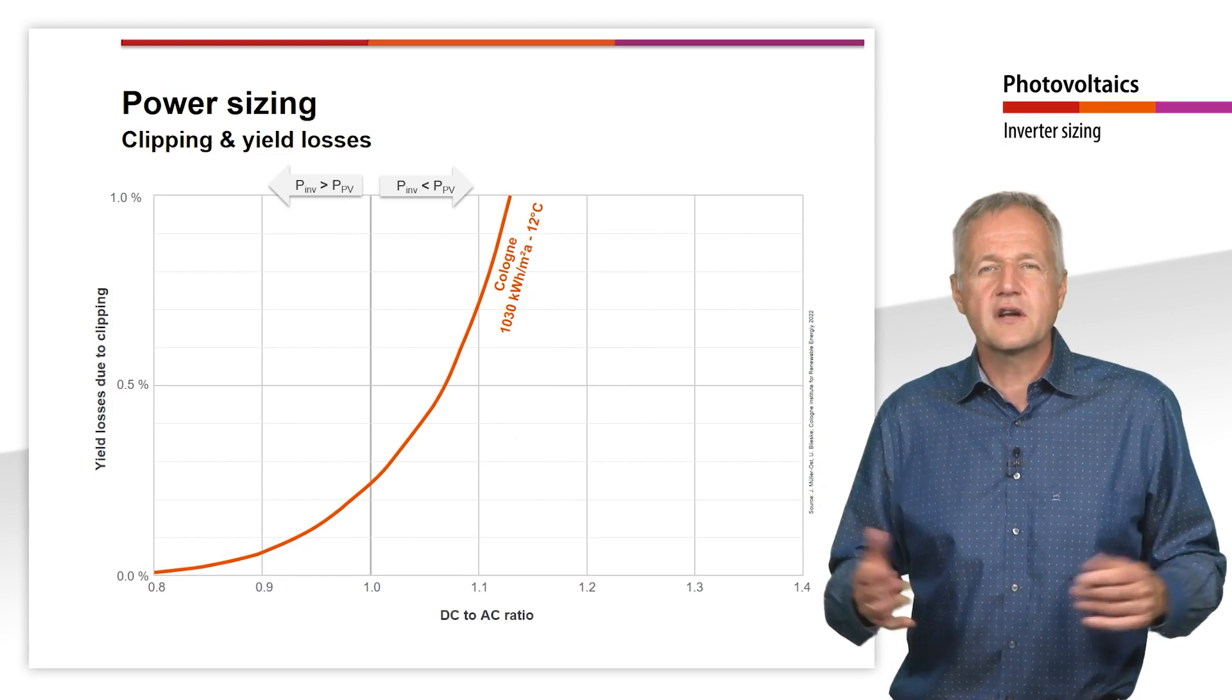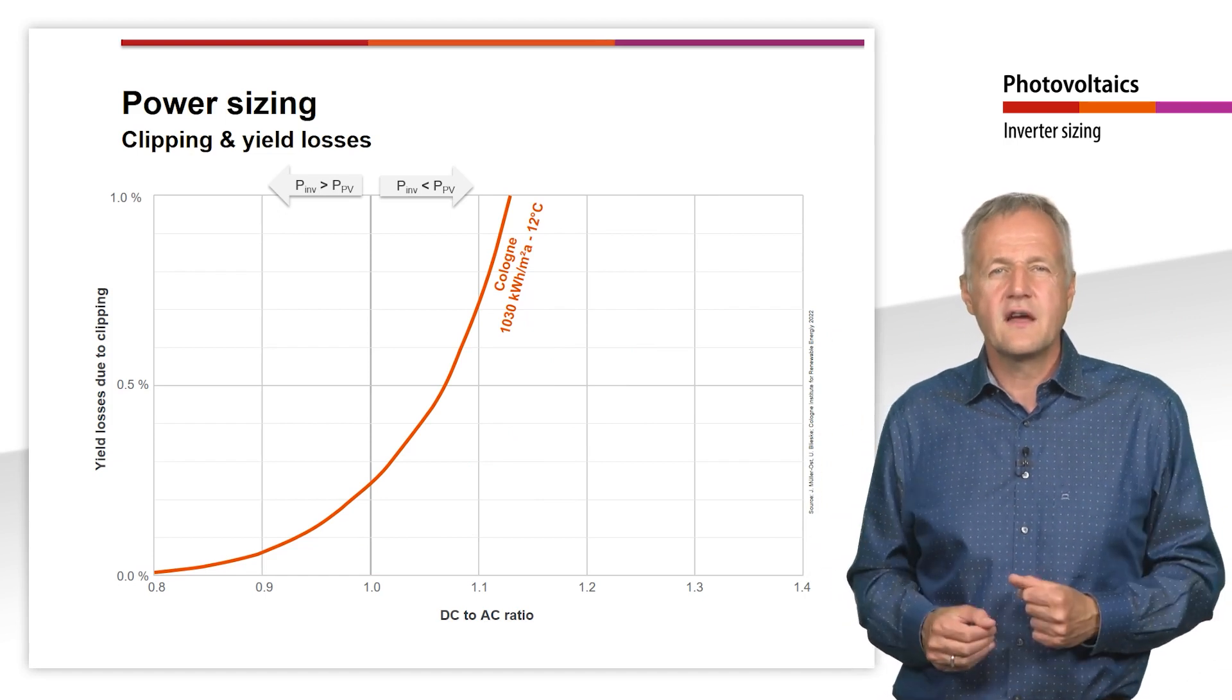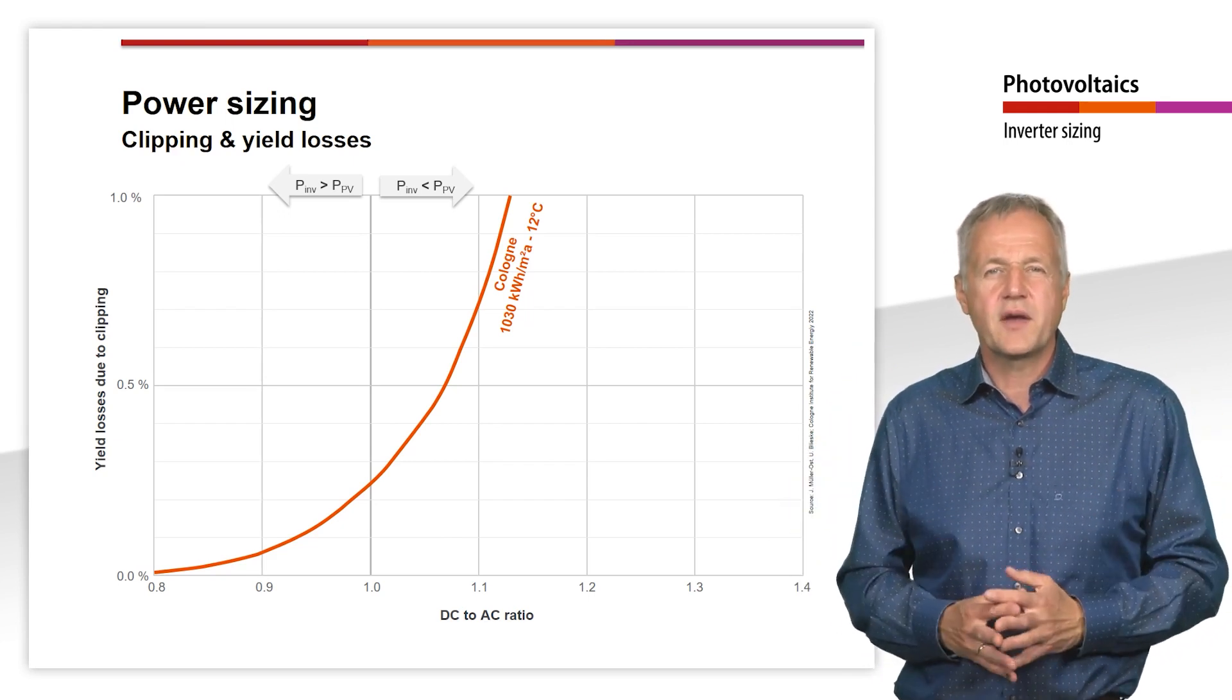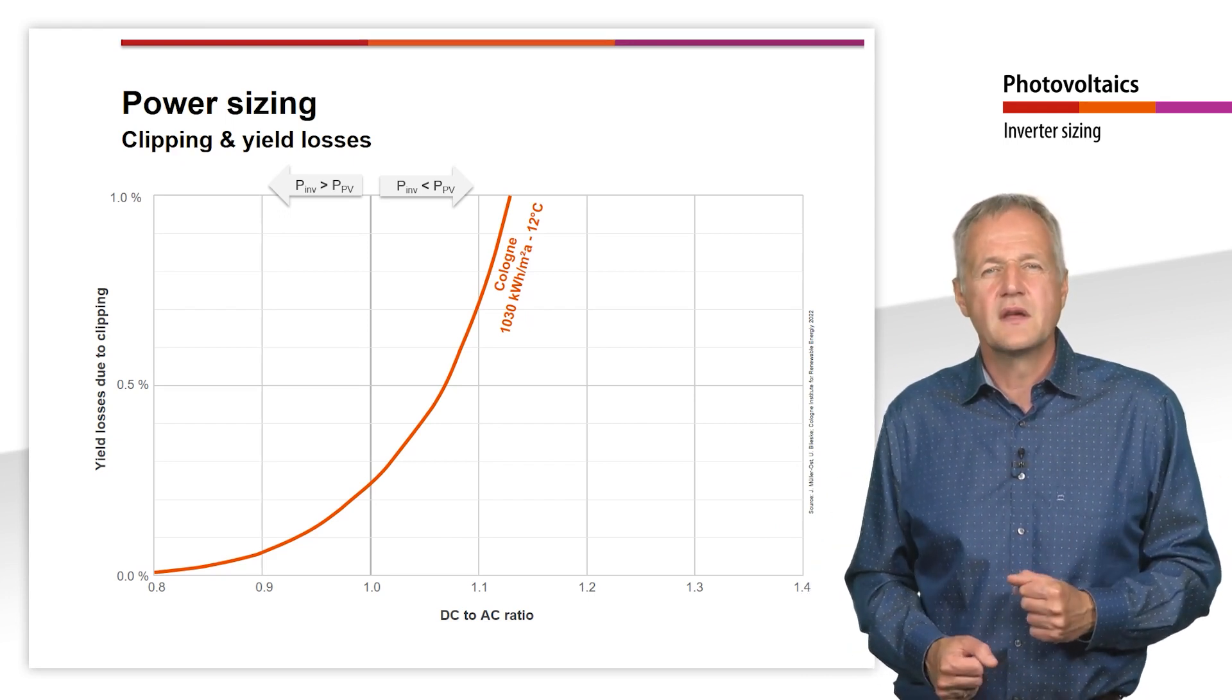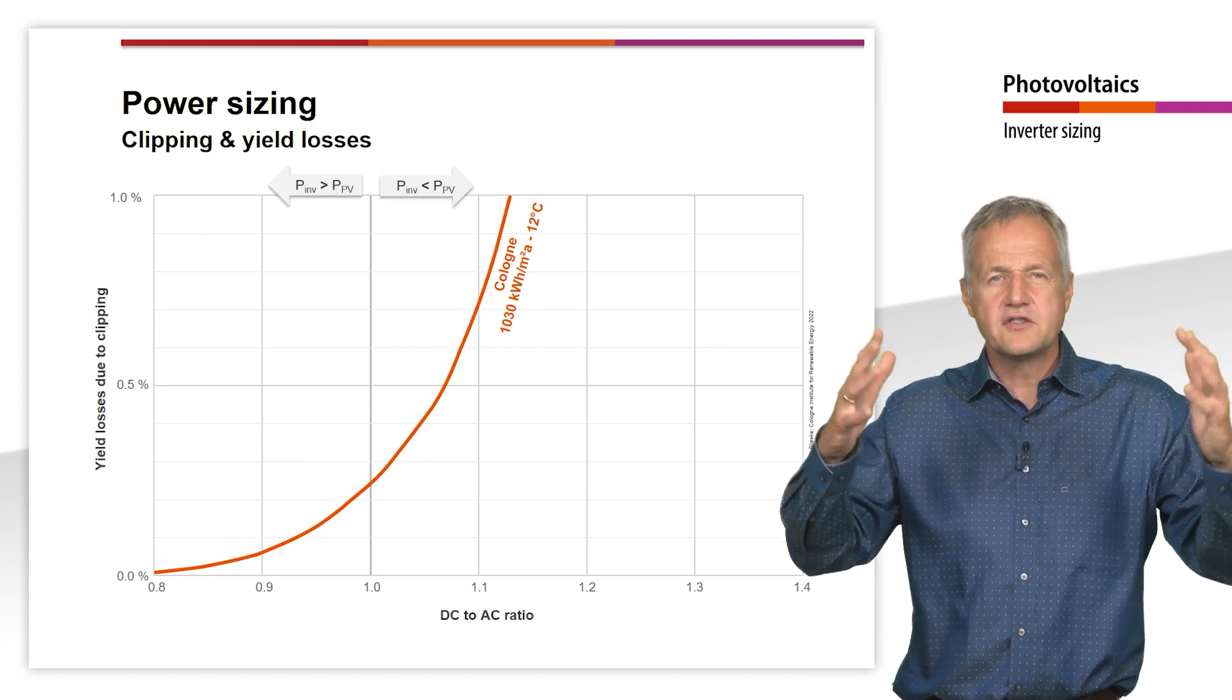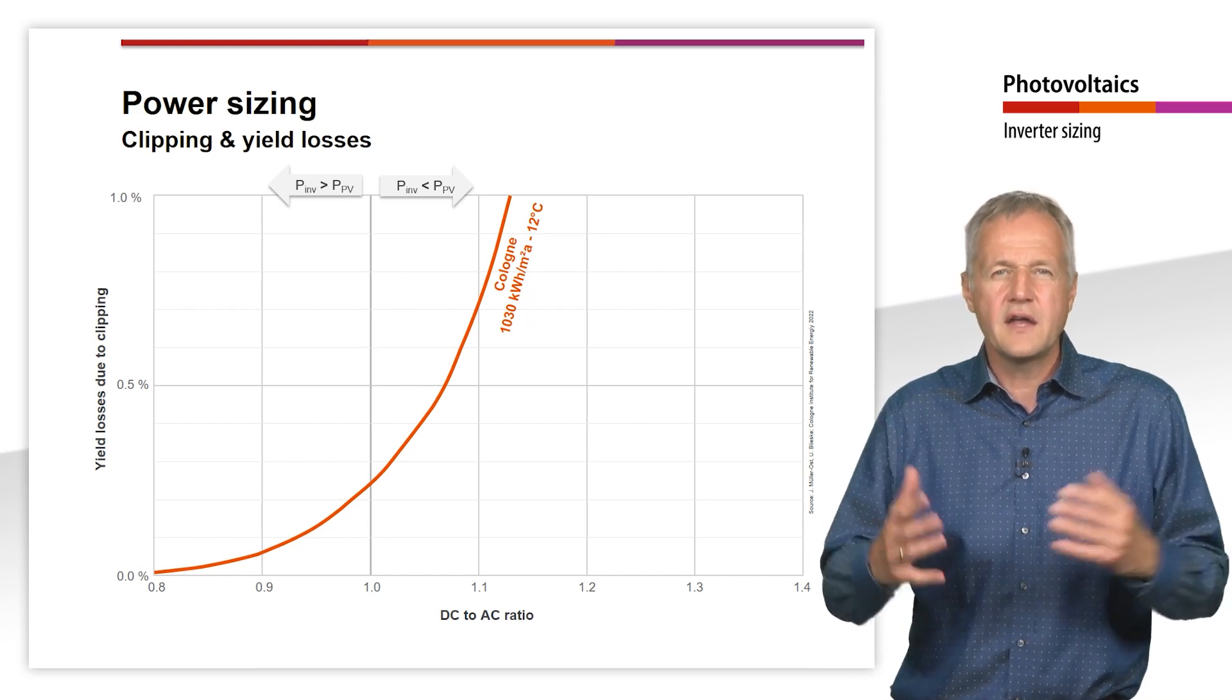In principle, an inverter can of course also be oversized. However, this only makes sense in very few cases, namely when a very high irradiance with simultaneously low temperatures can be expected for a significant time of the year. Examples of such a case are very irradiation-rich areas at high altitudes, since the modules heat up only slightly here due to the moderate temperatures despite high irradiance.